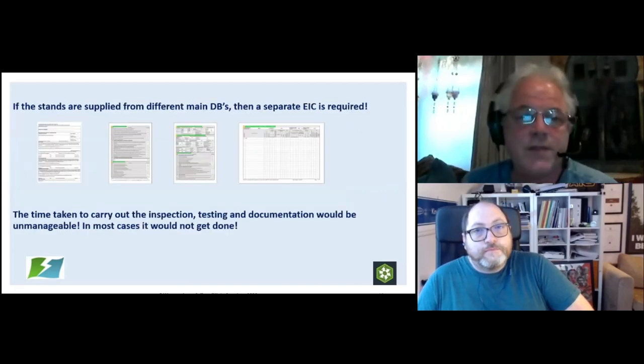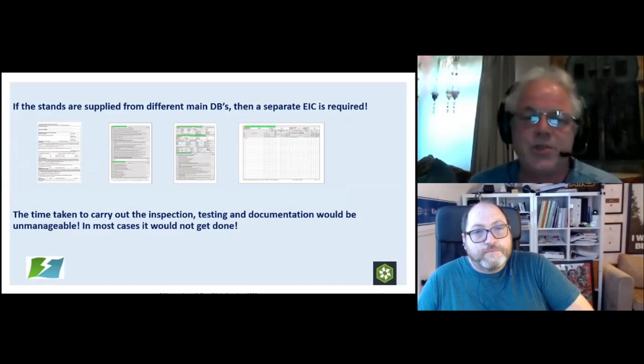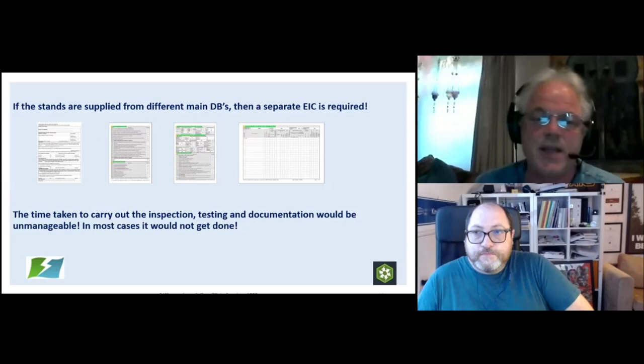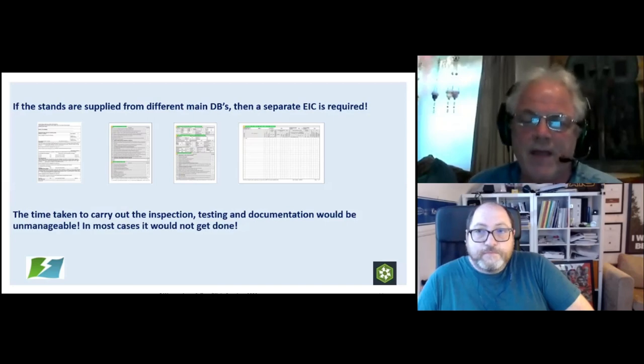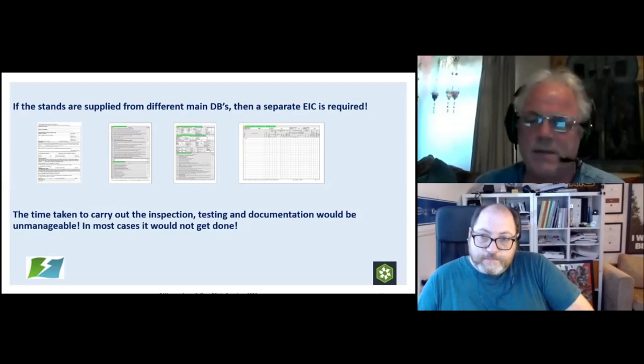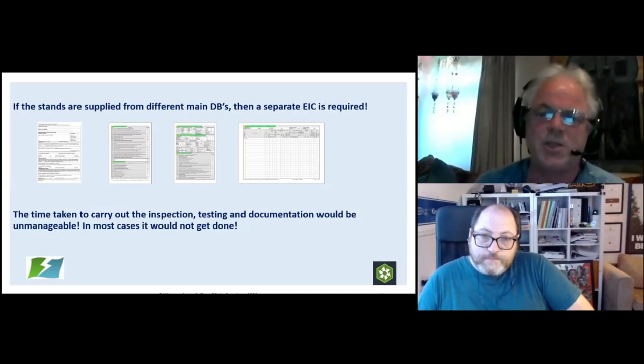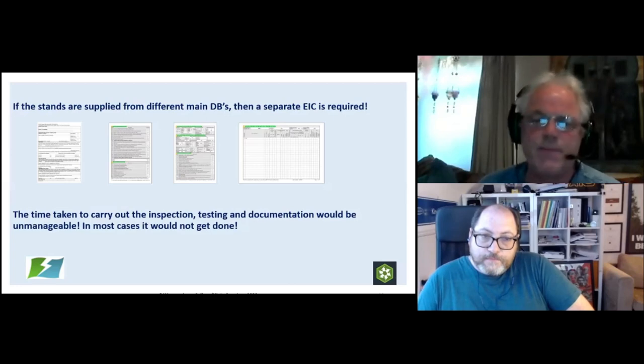Again, if you've got stands which are supplied from different main distribution boards, then you're going to require a separate EIC for every stand supplied from separate DBs. And this, again, is the actual time and effort you've got to put into doing a proper inspection and testing, and the documentation is unmanageable.